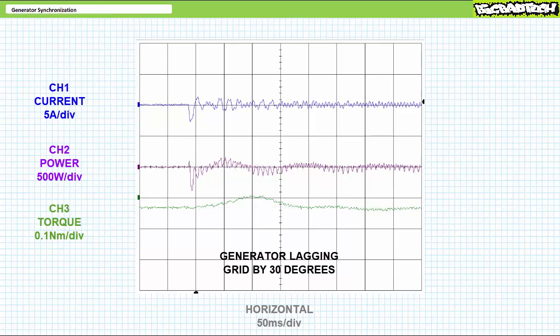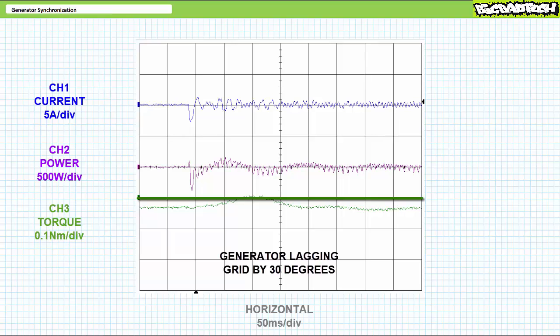Consider what happens when I close the contactor when the generator matches grid phase shift, frequency, and voltage, however the rotor is lagging 30 degrees behind the stator at the time of closure. Electrically, there's a momentary surge of current and electrical power into the machine. Mechanically, the shaft experiences a surge of clockwise torque in the previously established direction of rotation. The rotor's behind and the grid says 'hurry up' and pulls it forward as would a motor. There are two zero crossings where it goes from a tiny amount of negative counterclockwise torque, goes clockwise momentarily, and then settles back to the original amount. Not the ideal scenario, but all in all, not too bad.